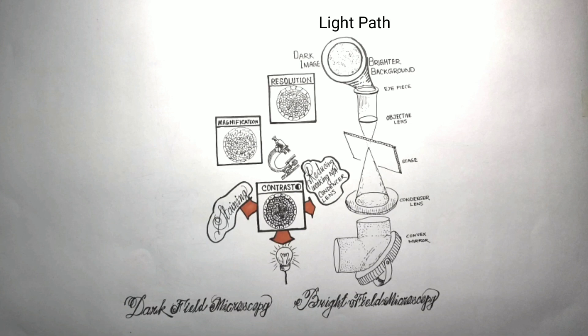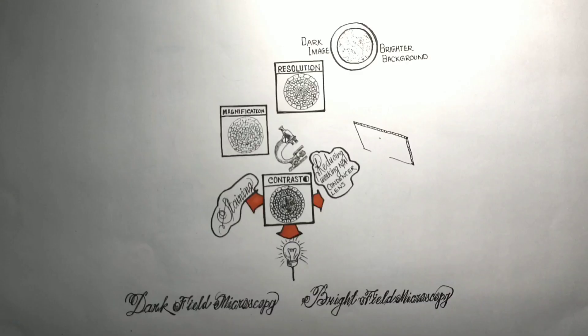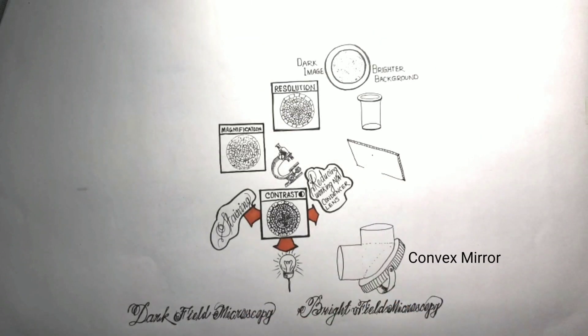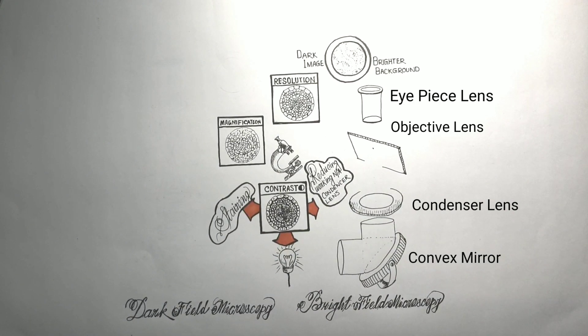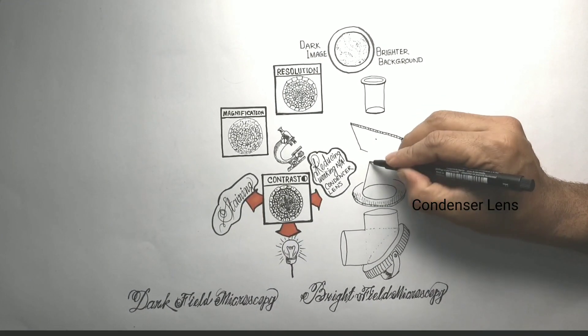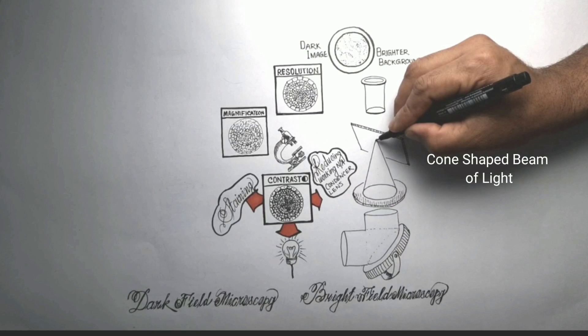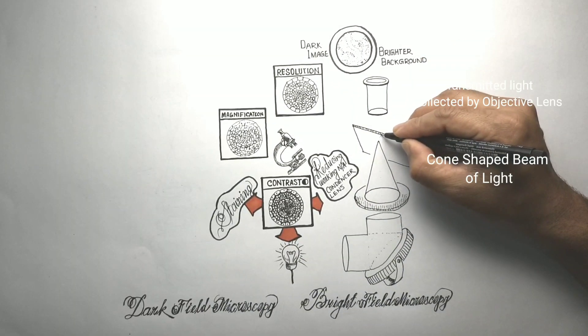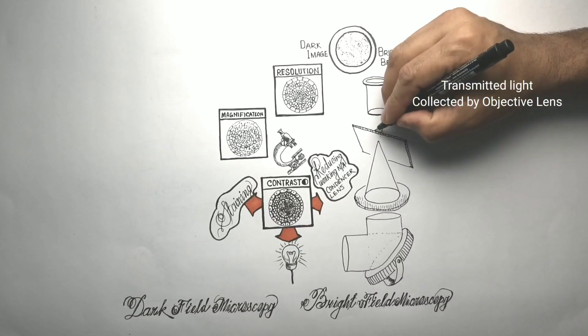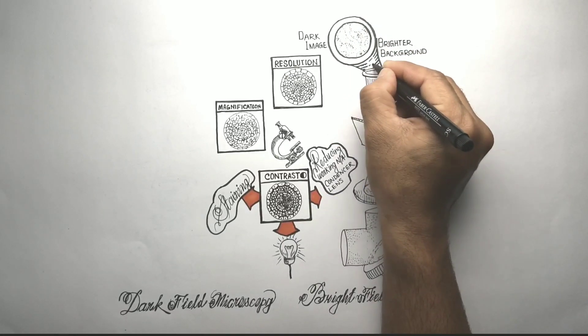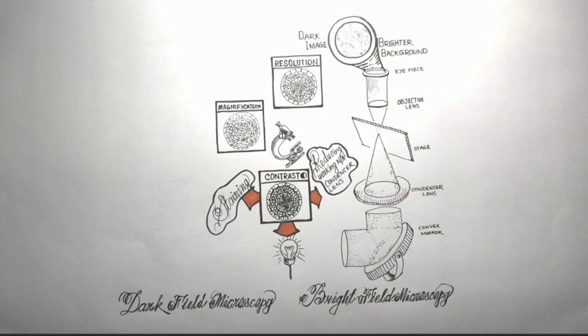Let's understand the light path in bright field microscopy. The light path is extremely simple and requires no additional components. Light from the source is aimed at the condenser lens by a convex mirror. The condenser lens focuses a cone-shaped beam filled with light onto the specimen. Light passes through the specimen and is collected by the objective lens above the stage. The image formed by the objective lens is then magnified by the ocular lens or eyepiece to form an enlarged image in the user's eye.